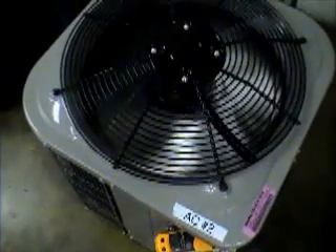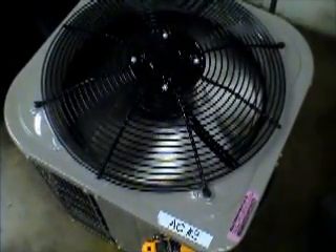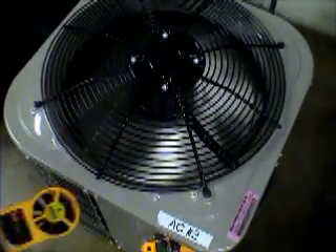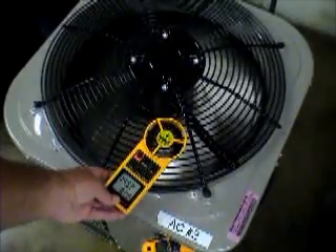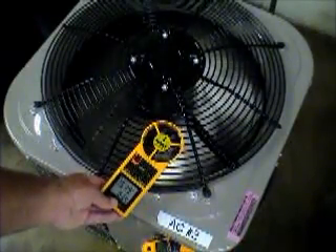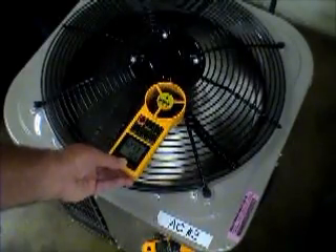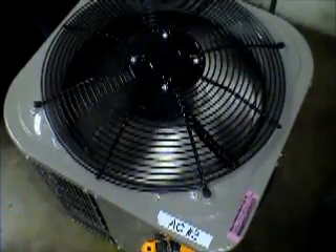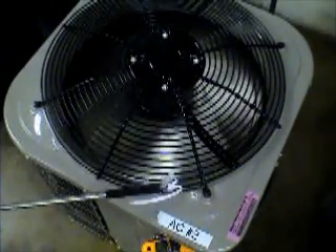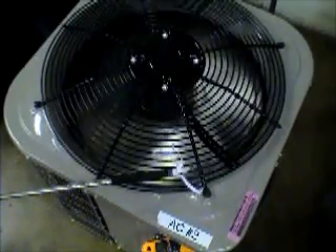I've got a vane anemometer and for visual I've got some strips of paper on the end of a wire. We're set up for feet per minute. You can see we're running about an average of about 1,500 feet per minute. And as we get towards the center it slightly slows down. Now I'm going to use the strips of paper. There isn't hardly any movement out towards this end at the tips of the blade.